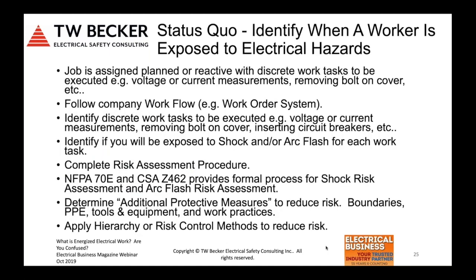So status quo, when is a worker exposed to electrical hazards? And to me, this has always been about the job assigned to workers and then the discrete work tasks. And a company would have a workflow, like some form of a work order system, formal or informal. Workers that do maintenance are assigned work. There's supervision, there's direction. Again, those work tasks are discrete work tasks under a job. So the motor's not running. I may have to open up a hinge door. I would be doing voltage measurements at possibly both AC and DC. And the worker needs to identify if they're exposed to arc flash and shock hazards. Complete a risk assessment procedure.